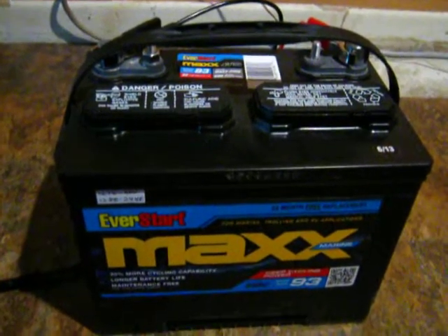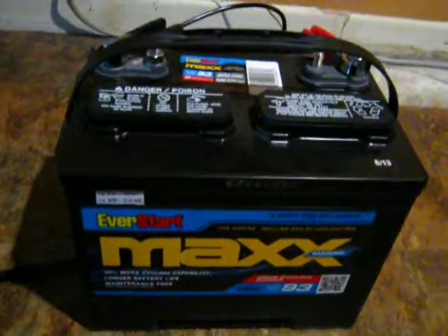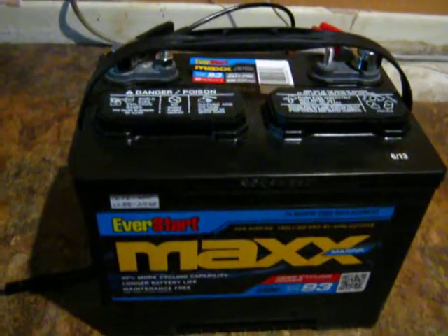Watch your fluid levels too. These caps pop off — distilled water only. Make sure it's fully charged first, then add the water after it's fully charged because it does expand a bit. The volume will increase when the battery is fully charged, so if you fill it up when it's half dead and then charge it, you could be spilling over a bit.